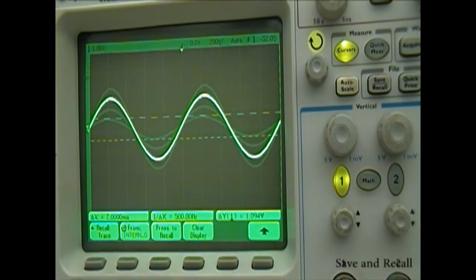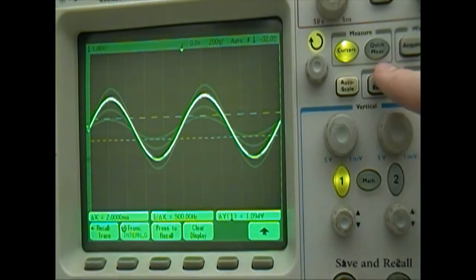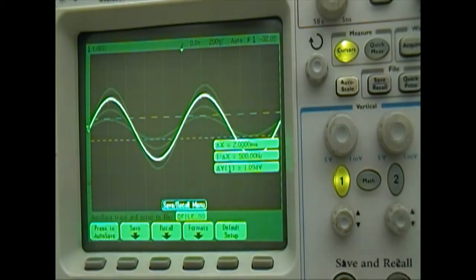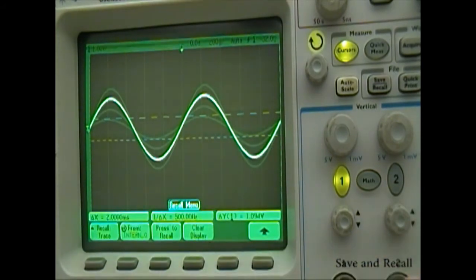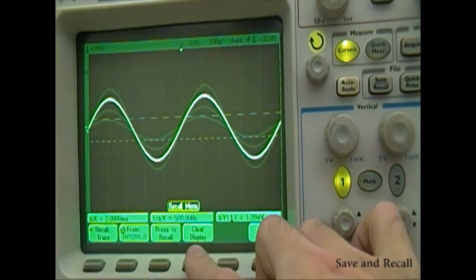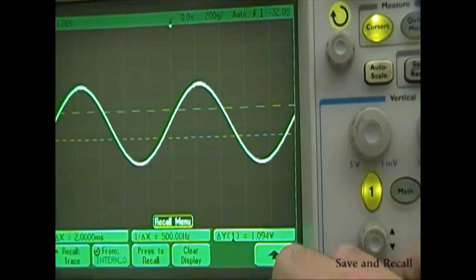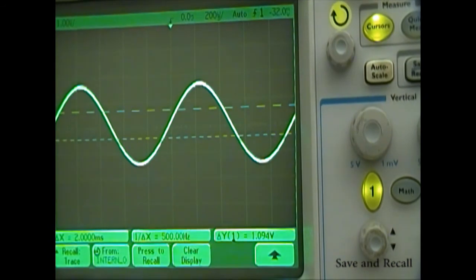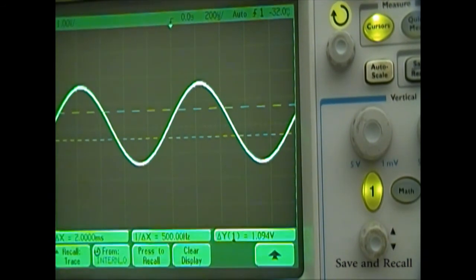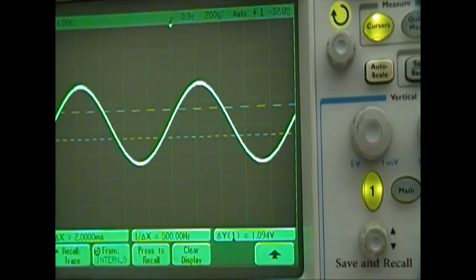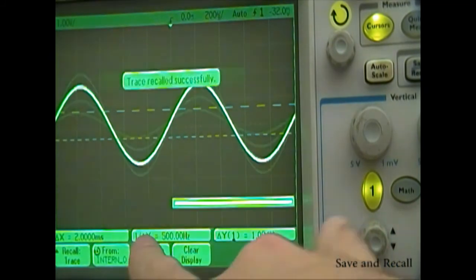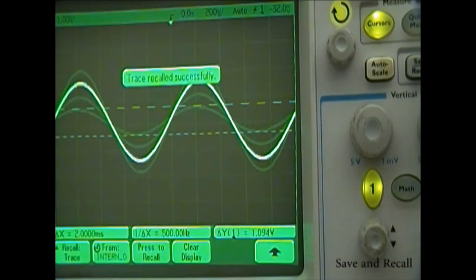This feature does have a disadvantage in that the recalled waves are very faint compared to the current waveform. To clear the recalled waves, press the Save Recall button and select the Recall option, then select the Clear Display option. Keep in mind that each time you save the display, it saves everything on the screen including the recalled waves. Thus, if we recall our last save, all the images will reappear.